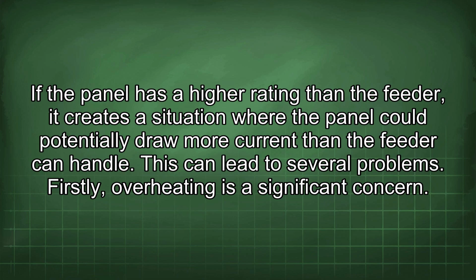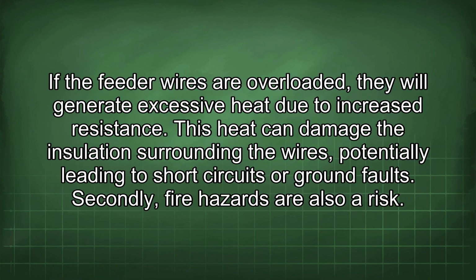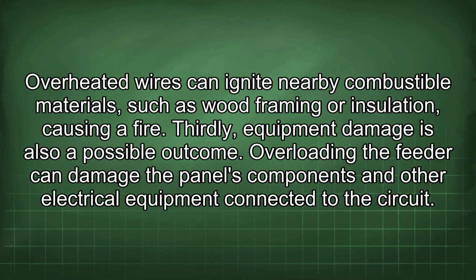This can lead to several problems. Firstly, overheating is a significant concern. If the feeder wires are overloaded, they will generate excessive heat due to increased resistance. This heat can damage the insulation surrounding the wires, potentially leading to short circuits or ground faults. Secondly, fire hazards are also a risk. Overheated wires can ignite nearby combustible materials such as wood framing or insulation, causing a fire. Thirdly, equipment damage is also a possible outcome. Overloading the feeder can damage the panel's components and other electrical equipment connected to the circuit.